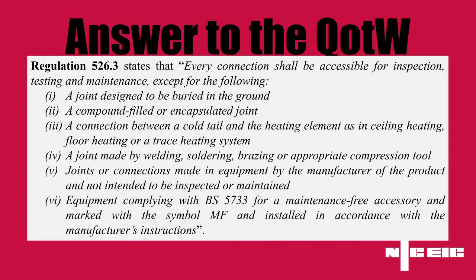Regulation 526.3 gives you a detailed list of everything that requires inspection, because if it's not within the 6 items you see on the screen, it requires inspection and future maintenance. Anything on that list does not require it. The simple reason comes from the manufacturers - they allow, through their instructions, their product to be designed in such a way that when connections are made, there's no risk of the cables or conductors getting loose in the terminals, which gives us comfort that the connection will be permanent.